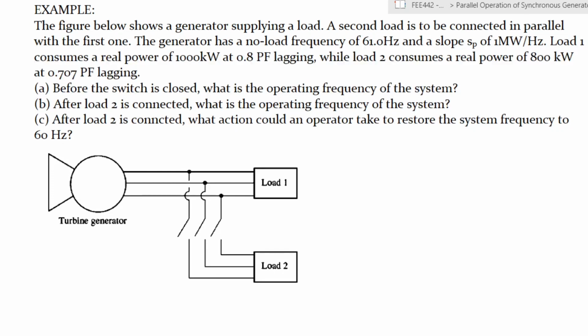reactive power. So you have a generator with a no load frequency of 61 Hertz. That is the set point that you have set for this particular instance. The slope is given by 1 megawatt per Hertz. So for every megawatt increase, there's a 1 Hertz drop in frequency, right?